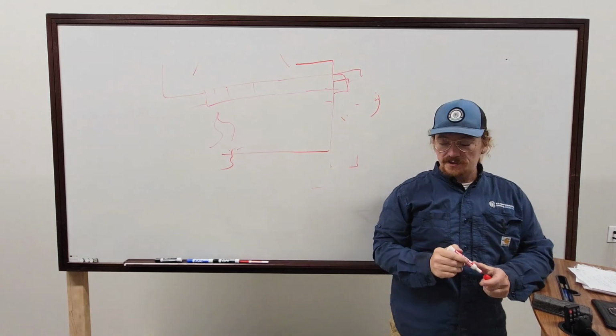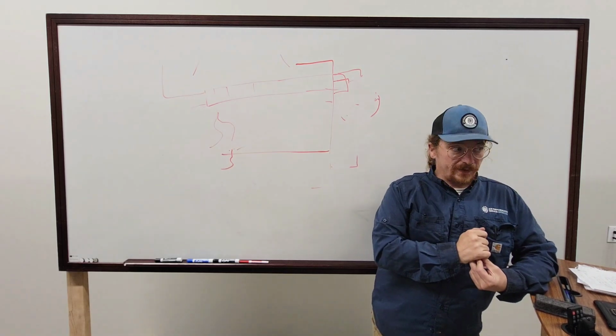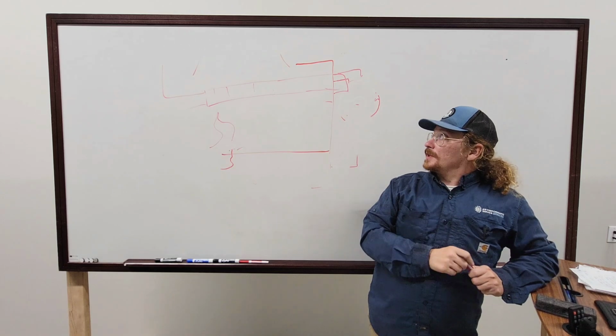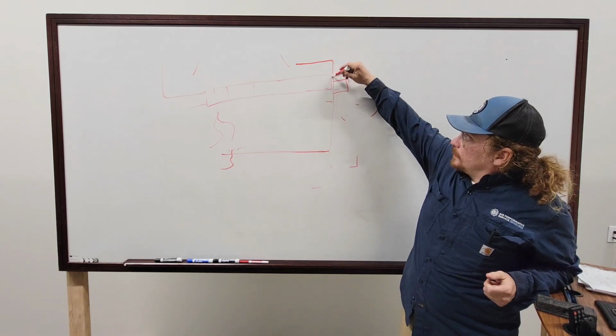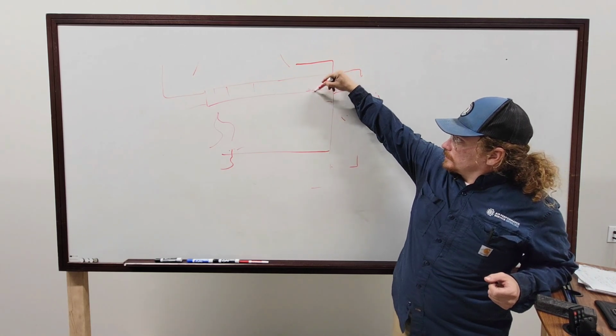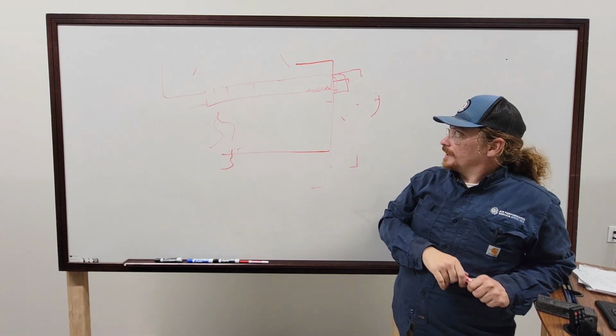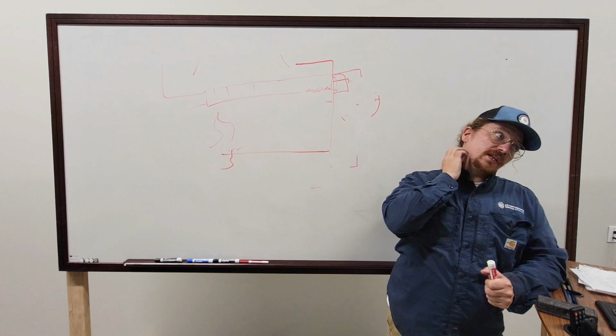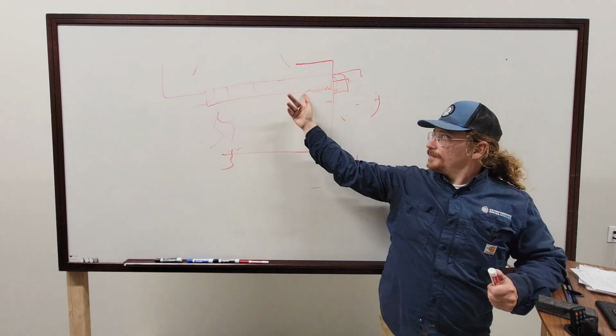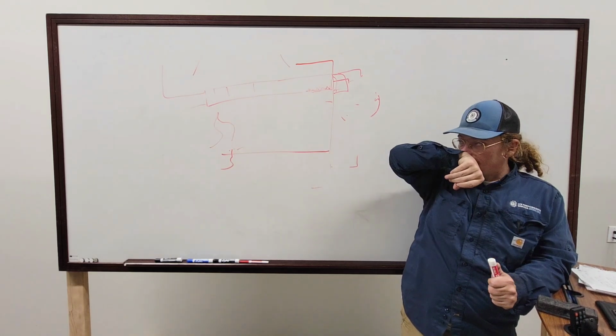Like when you're doing your maintenance, if you were to look up at a water tube boiler, and this is common in copper, the Lochinvar has a copper fin, and that's a water tube boiler. What is typical is these will leak here at this flange, and you'll see a lot of corrosion. And of course, corrosion being a great insulator, it really messes with the boiler operation. And so that's going to create a lot of excess CO that goes out the vent. Any sort of corrosion on this is going to really severely hurt it.